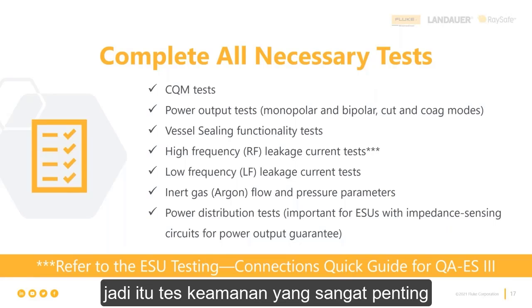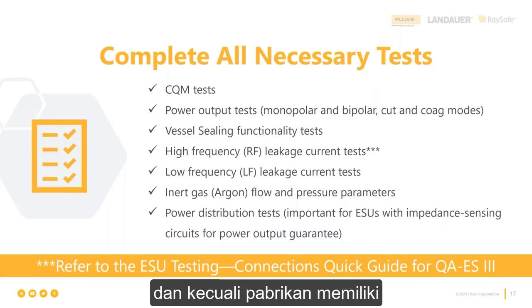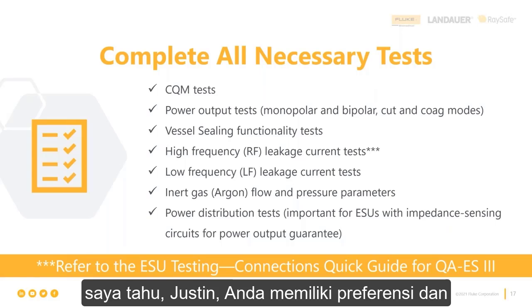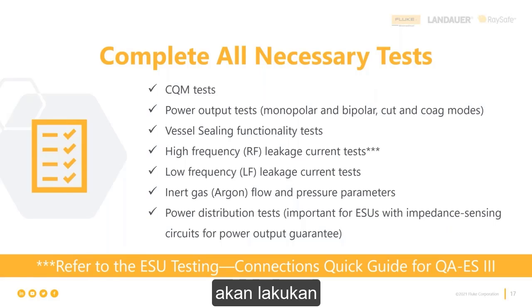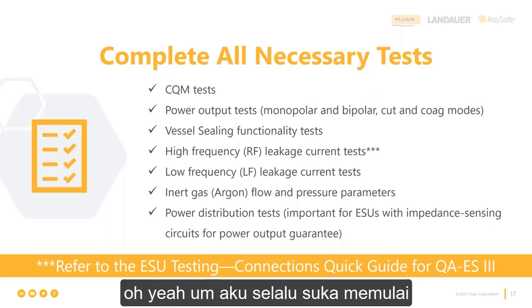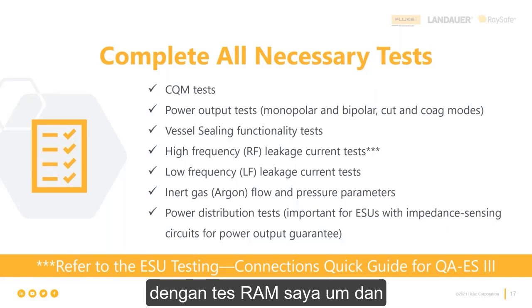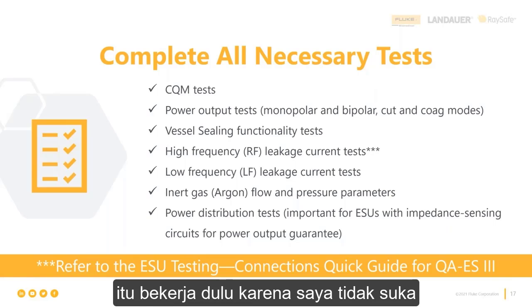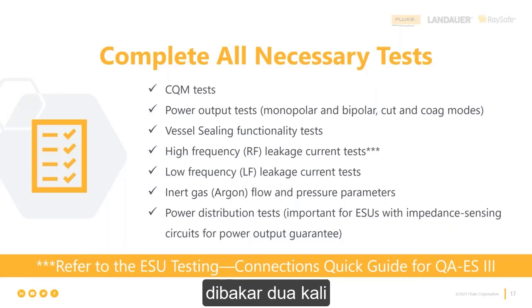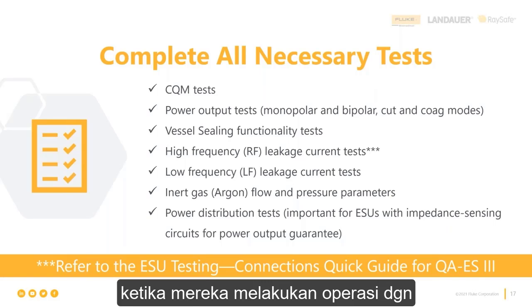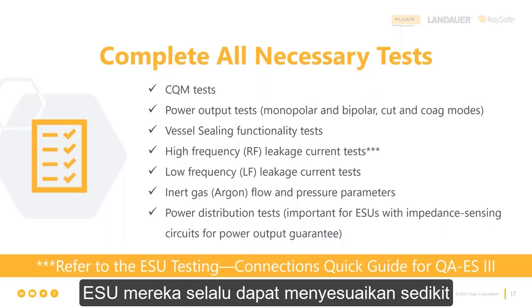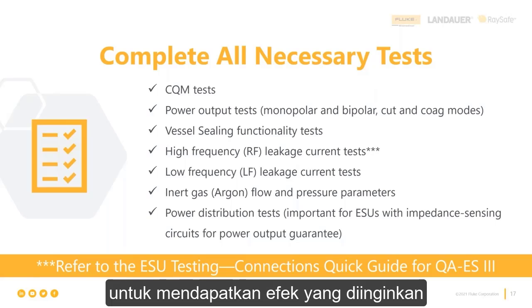So that's a really important safety test. And unless the manufacturer has a different flow and sequence, in other words, that test comes in a different place. I know, Justin, you have a preference, and this is one of the tests that you would do number one, yeah? Oh yeah. I always like to start off with my REM tests, and the reason is I want to make sure that works first, because I don't like being burnt twice. You know, when they're operating an ESU, they can always adjust a little bit to get the desired effect.